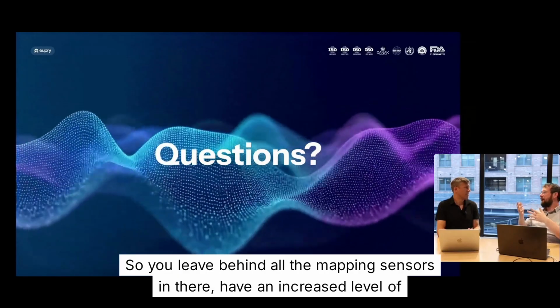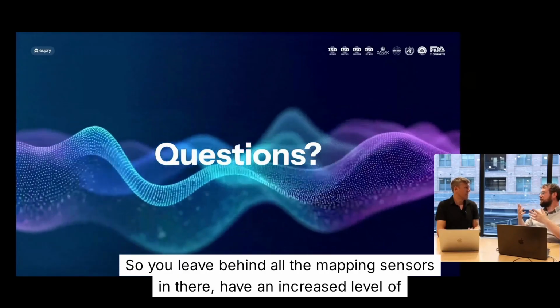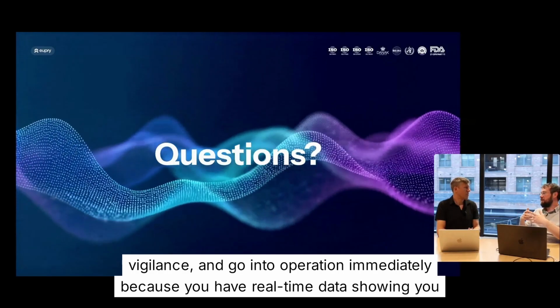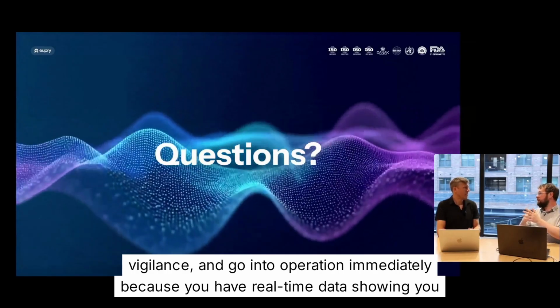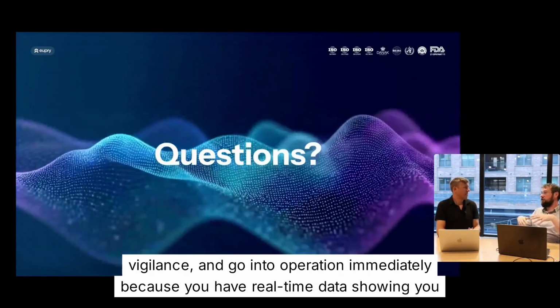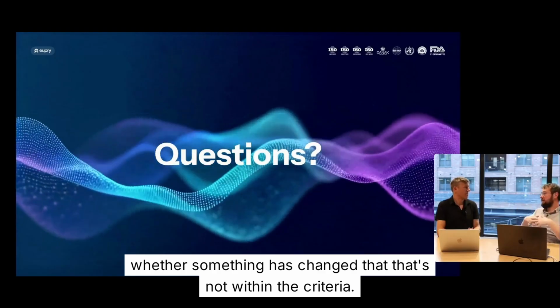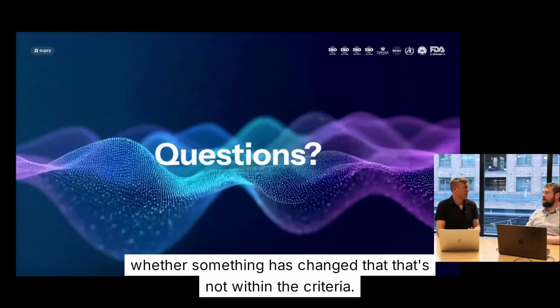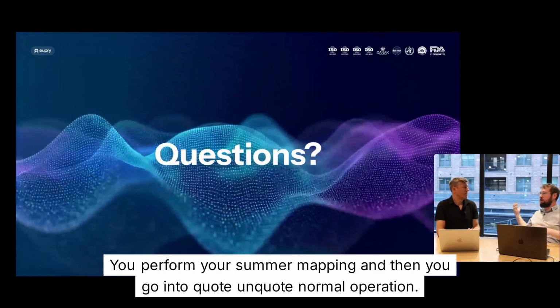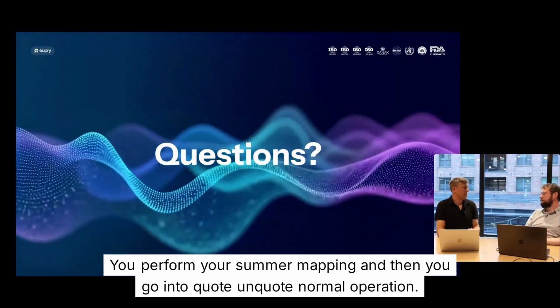So you leave behind all the mapping sensors in there, have an increased level of vigilance, and go into operation immediately, because you have real-time data showing you whether something has changed that's not within the criteria. You perform your summer mapping, and then you go into quote-unquote normal operation.